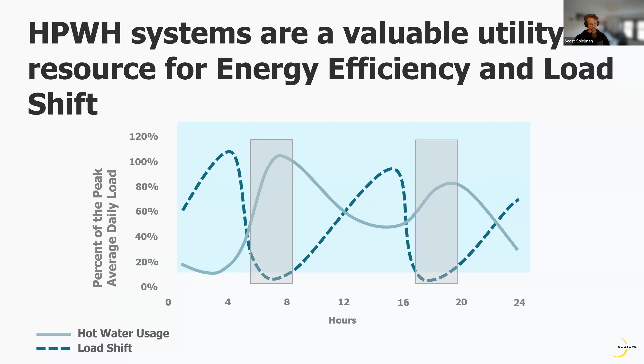So in this diagram here, it's kind of like a schematic diagram. We show that hot water usage shape in the light blue solid line. And then that load shift dash line is a representation of what we're trying to get to on the electrical side when we shift load. So if we wanted to shift load away from morning peak and evening peak hours, those line up perfectly with when hot water is used. But because we have that large thermal storage volume, we can shift when electricity is used to just before those large peaks.